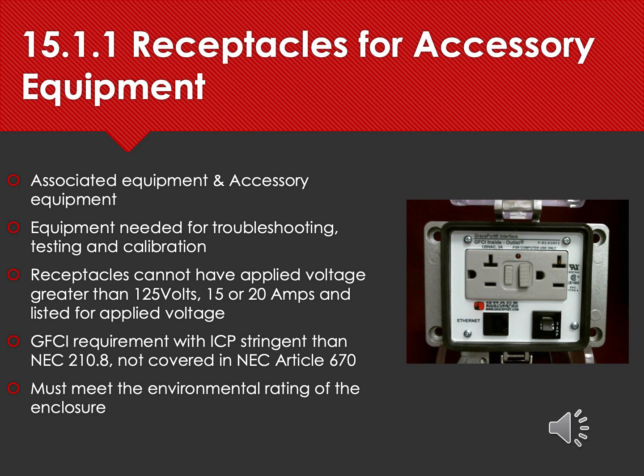And next thing is, receptacles used in machinery cannot be rated for more than 125 volts AC. And only 2 receptacle configurations are allowed to be used per NFPA 79. One is 15 amps, another one is 20 amps, okay? Also, the receptacle must meet the environmental rating of the enclosure for listing and labeling requirements of the panel itself, okay? Given the nature of the industrial machinery, the type of operating environments, and also taking the personal interaction with the panel, any receptacle intended for maintenance personnel must have GFCI protection per NFPA 79, period.